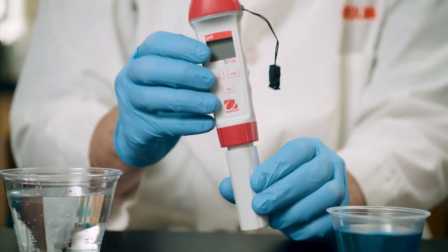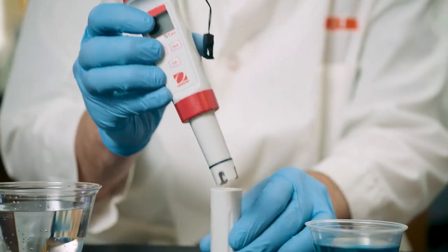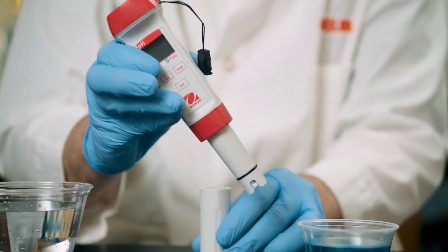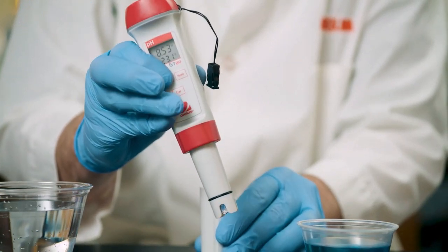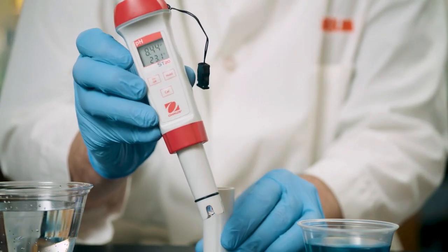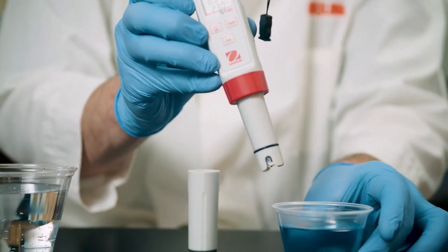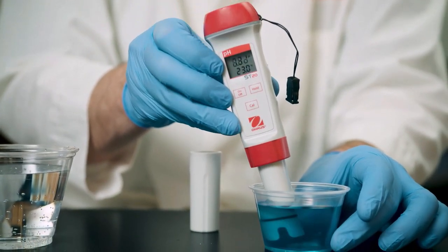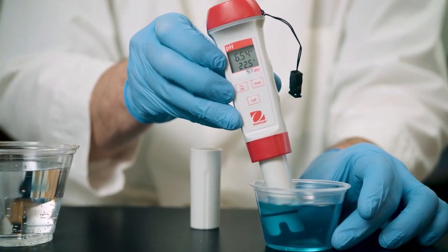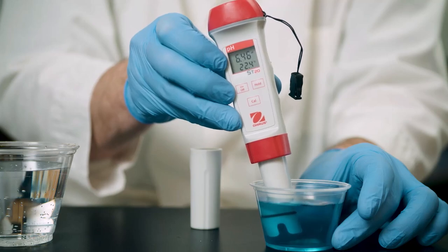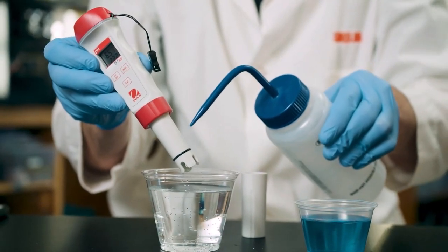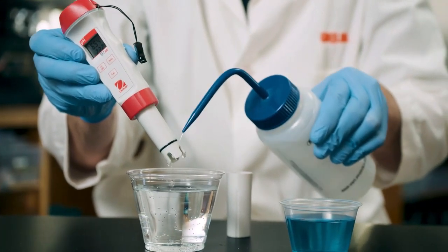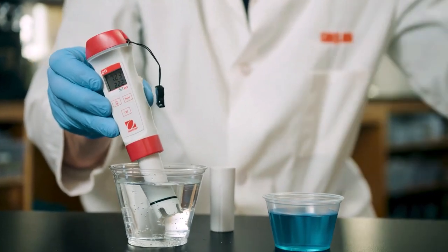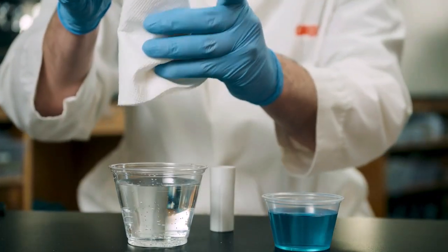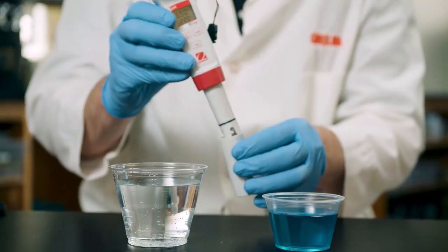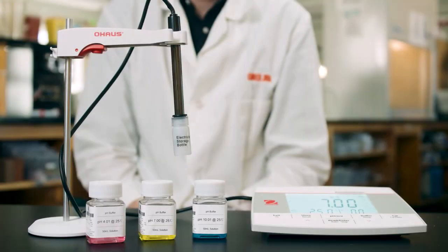To use a pH pen meter, first remove the protective cap. Then press the on-off button. Dip the electrode 2 to 3 centimeters into the solution so the bulb of the electrode is covered. Wait until the reading is stabilized. Record the reading. Rinse the electrode with distilled water and wipe clean. Repeat this process as needed to take all your required readings. Once finished, press and hold the on-off button to turn off the meter.